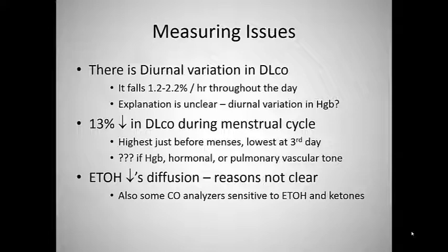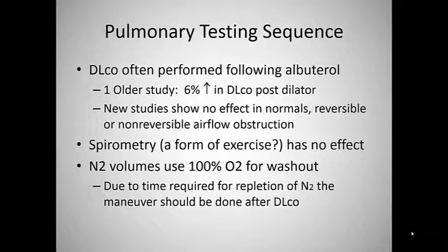People that come in, we all have alcoholic patients, you kind of smell the alcohol. It's kind of interesting. Pay attention to that sometimes. If you have spirometry and diffusion, and you had a previous number, if you smell the alcohol, I bet you anything your diffusion's a lot lower. I've seen that coincidentally a lot over the years, and then you just have to blow it off and ignore it at that point. Sometimes it interferes with the analyzers also.